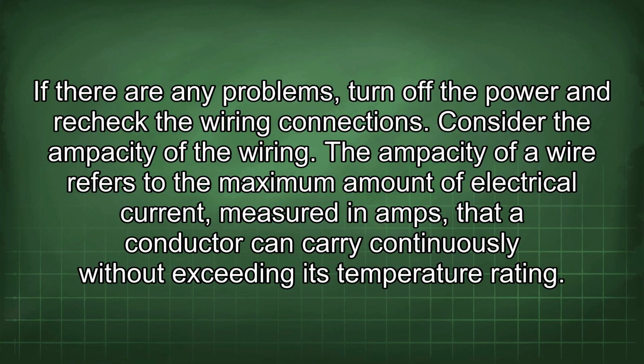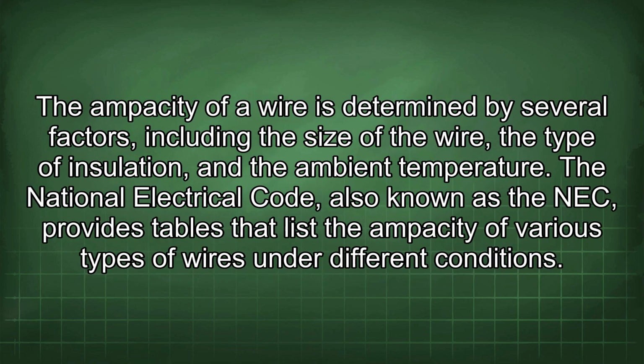Consider the ampacity of the wiring. The ampacity of a wire refers to the maximum amount of electrical current, measured in amps, that a conductor can carry continuously without exceeding its temperature rating. The ampacity of a wire is determined by several factors, including the size of the wire, the type of insulation, and the ambient temperature. The National Electrical Code, also known as the NEC, provides tables that list the ampacity of various types of wires under different conditions.